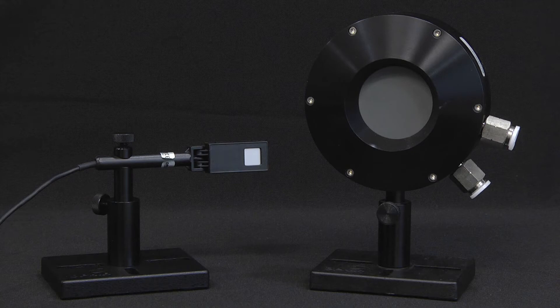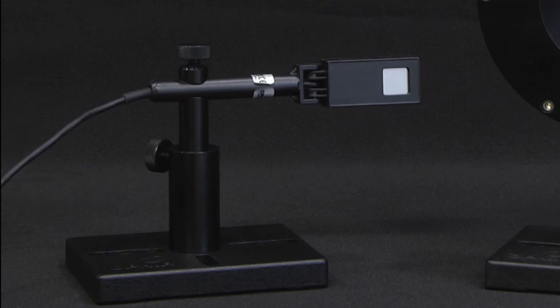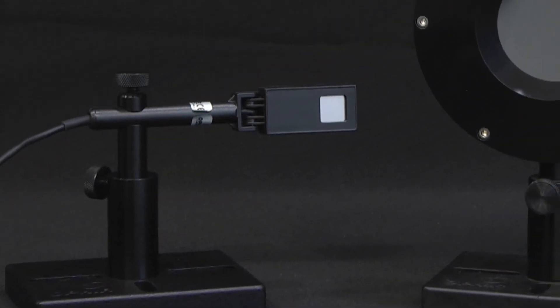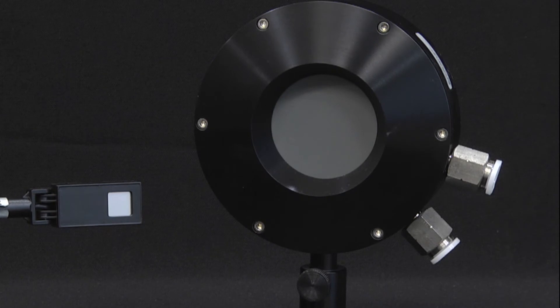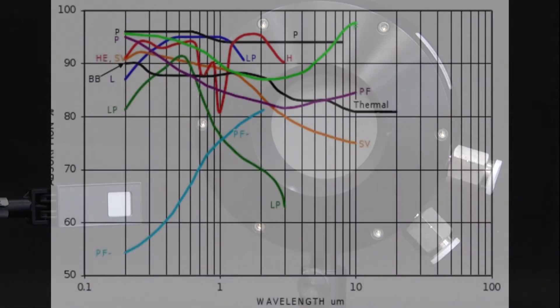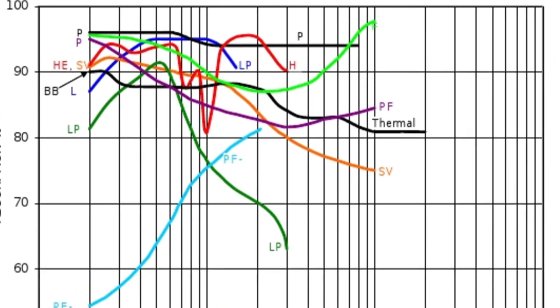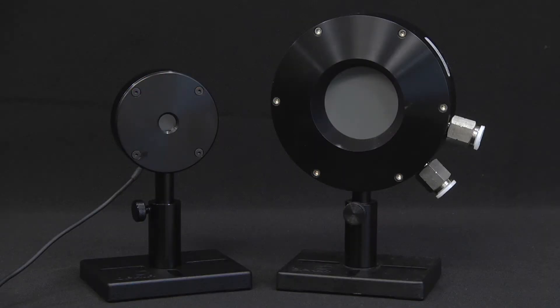The choice of sensor depends on a number of parameters, including the order of magnitude of power. For example, a sensor that can measure picowatts will probably be vaporized into plasma by a multi-kilowatt industrial beam, while a sensor able to measure multi-kilowatt beams will not likely respond at all to a few picowatts. Spectral region. Different materials absorb light of different wavelengths to varying degrees. And beam diameter.